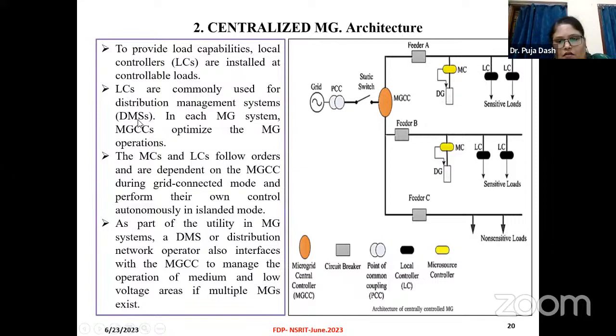The main microgrid controller unit optimizes the operations. The micro resource controllers and the local controllers follow the orders of, and are dependent on, this particular MGCC, the microgrid central controller, in this controlling scheme, and perform their own control autonomously in island mode. As part of the utility of the microgrid system, the DMS or distribution network operator also interfaces with the MGCC to manage the operation of medium and low voltage areas if multiple MGs exist. So this is the simple configuration and the working operation.